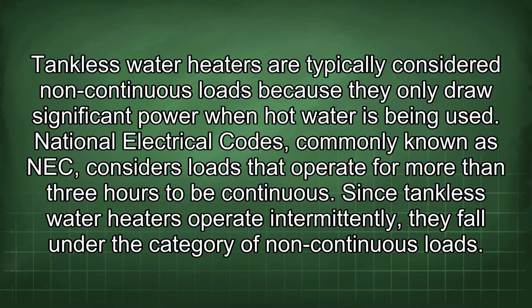Tankless water heaters are typically considered non-continuous loads because they only draw significant power when hot water is being used. The National Electrical Code, commonly known as NEC, considers loads that operate for more than 3 hours to be continuous. Since tankless water heaters operate intermittently, they fall under the category of non-continuous loads.